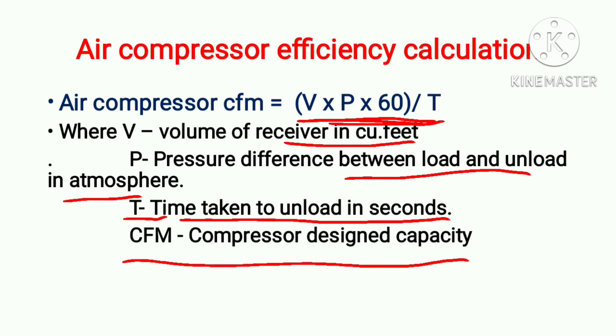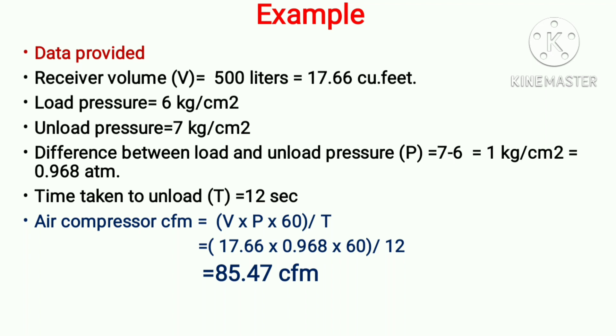Now we will calculate using an example. The receiver volume is taken as 500 liters — generally receiver volumes are provided in liters, so we convert to cubic feet. 500 liters converts to 17.66 cubic feet. The load pressure is 6 kg and the unload pressure is 7 kg.